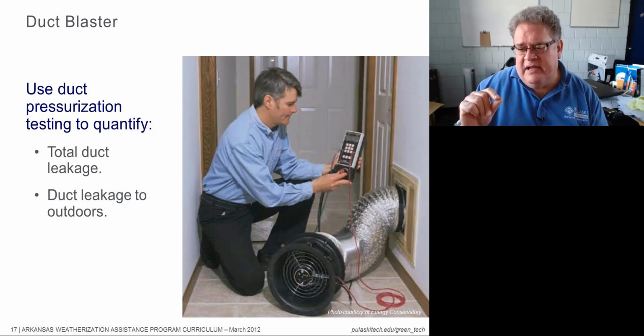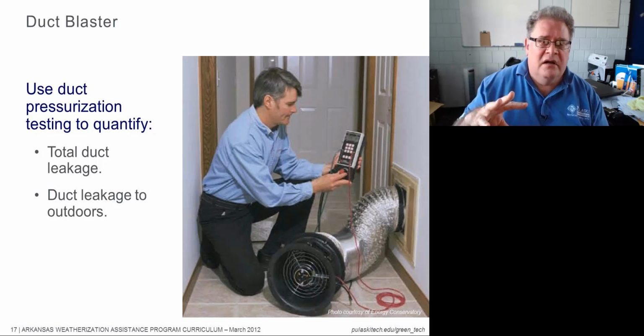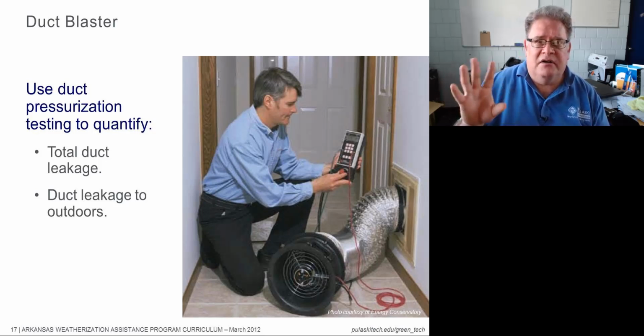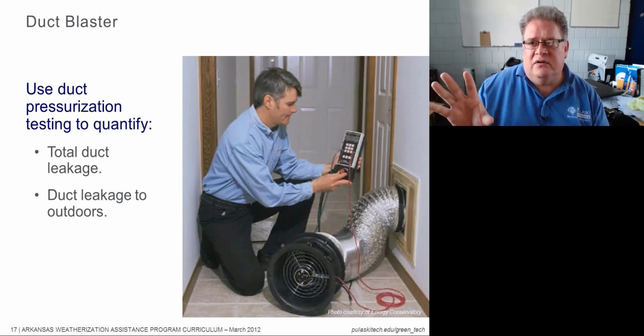Whereas a pressure pan just says, yes, there's leakage and it's bigger or smaller. It's kind of like playing the game hot or cold. You know, you're getting warmer, you're getting warmer, you're getting colder, you're getting colder. That's a pressure pan. However, a duct blower is a very accurate way of measuring ducts.